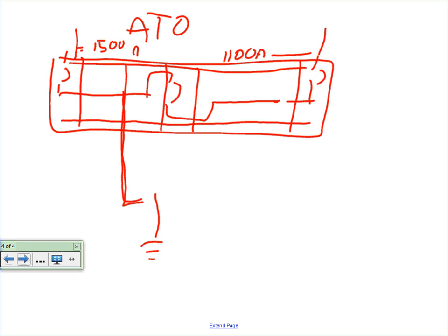Now, it makes it easier, right? Because that ground fault system could be very expensive, depending on how many relays and all that stuff we have to add to the system to account for neutral currents flowing back to both services. If we use 4-pole breakers at each of those locations, now we're switching the neutral as well to both sources, and we don't have to worry about that funky ground fault system, because now the neutral current can only flow either to that main or back to this main. And when you disconnect the tie, now you break that neutral, so whatever current's flowing here is going to go that way, and whatever current's flowing here is flowing that way.